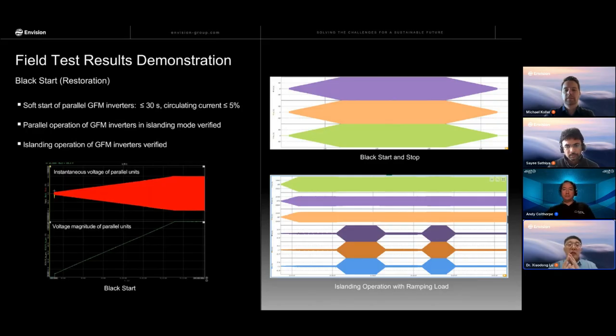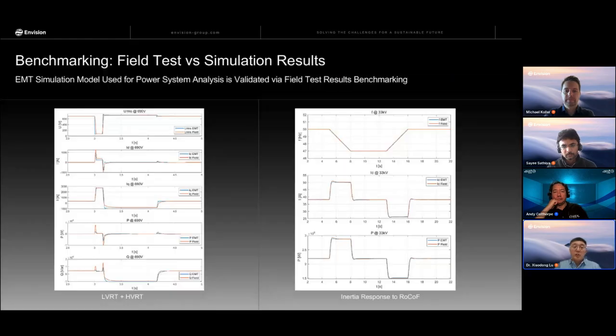We also tested the parallel operation in islanding mode, as I show on the right side. It's black start and black stop, and also black start with islanding operation with ramping load. That's pretty much it for the results demonstration. Besides that, after we got the data from on-site, we also used it to verify our control design in the simulation. As shown here, it's verified that our simulation matches the field result very well.